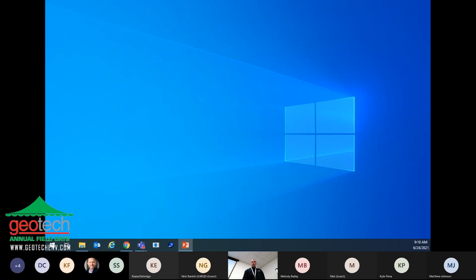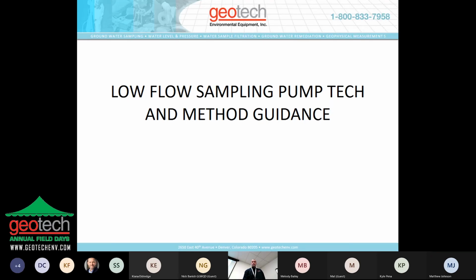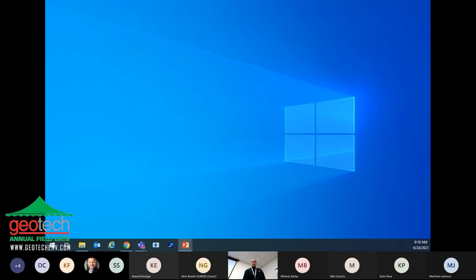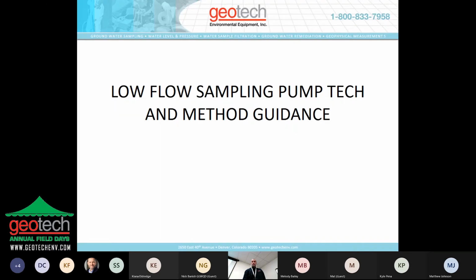Something else to add on suction lift specifications: if you go with a larger size tubing, size 15 is a small performance tubing with a max lift of 29 feet, but size 36 has a max lift at sea level of 26 feet. So review the spec sheet and understand your site characteristics, wherever you're sampling from, to make sure you're able to lift with the appropriate tubing and elevation.